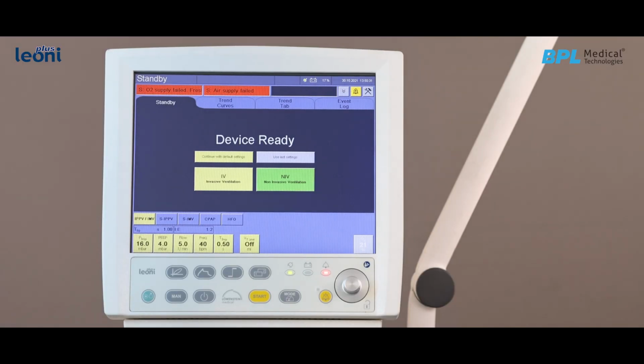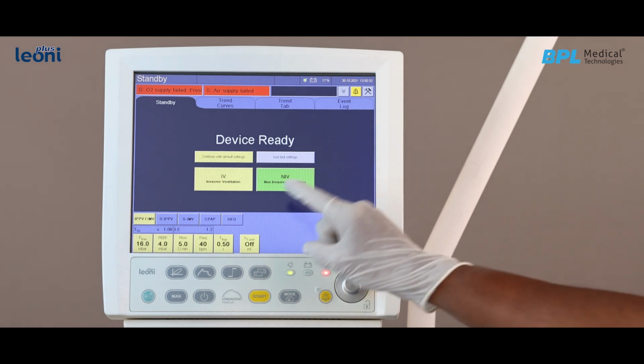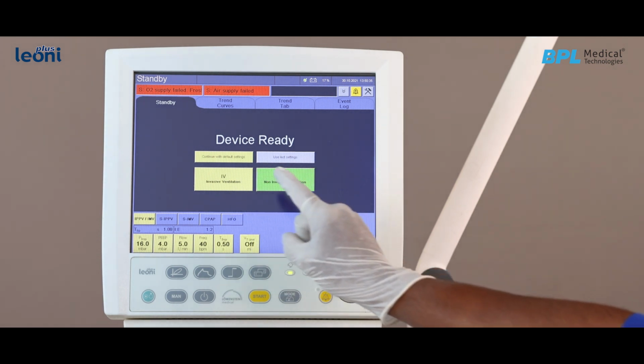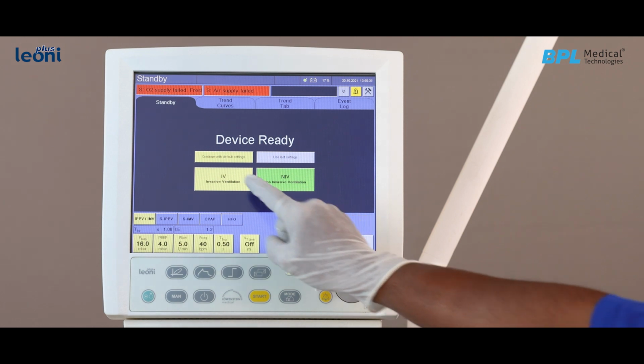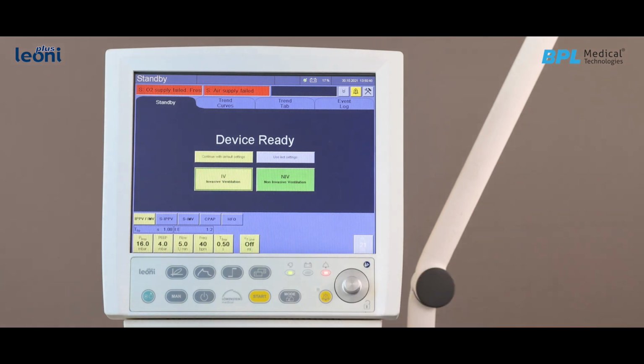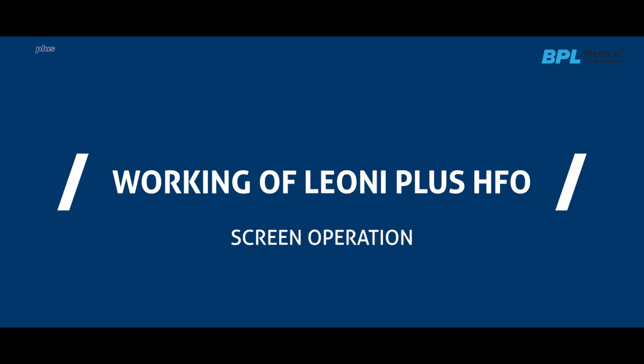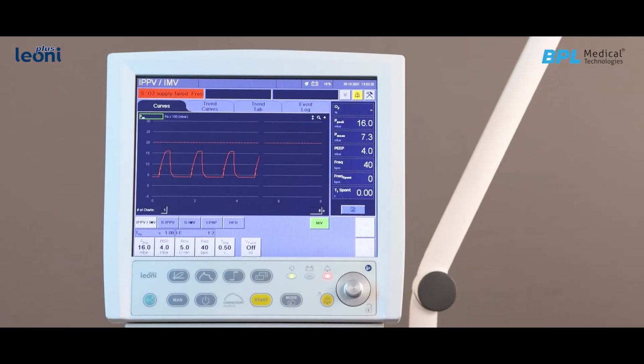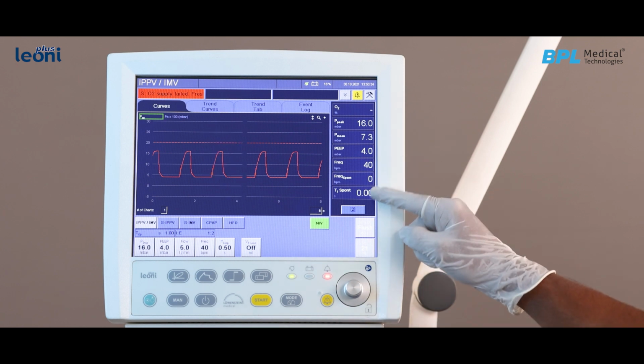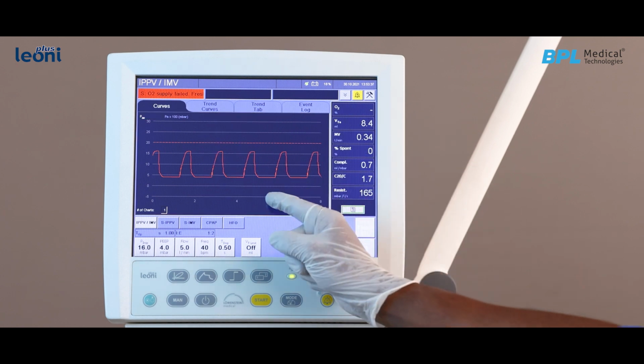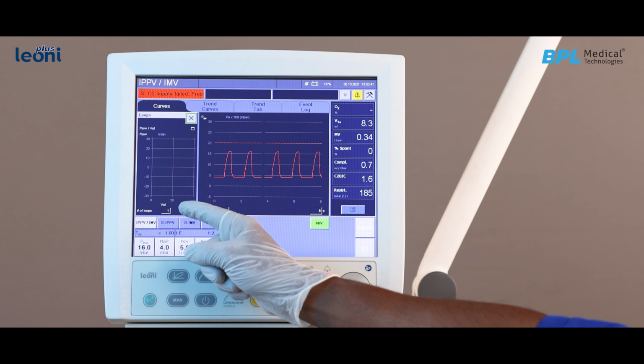In standby mode, the user will have the following options to select from: type of ventilation, invasive and non-invasive. Ventilation mode. Default settings are available with auto alarm settings. Press the start button to initialize the ventilation. The screen is mainly divided into 4 zones: ventilator control, monitoring and patient numeric parameter, waveforms and loops, alarm message area.